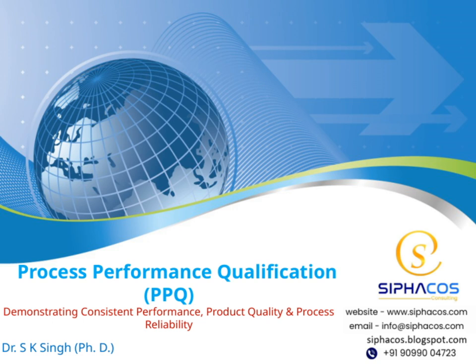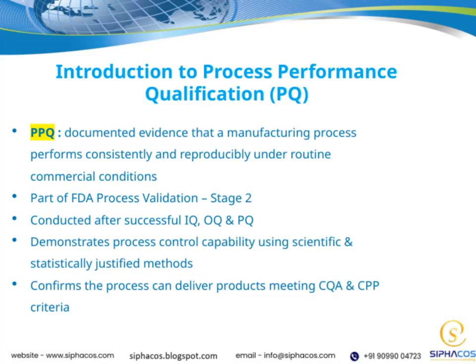So let's get started. Now, let's talk about PPQ, or Process Performance Qualification. This is the stage where we gather documented evidence to show that a manufacturing process performs consistently and reproducibly under routine commercial conditions. Essentially, it's about proving that the process is reliable in real-world production settings. This step is part of the FDA's Process Validation Framework, specifically Stage 2. It's conducted after we've successfully completed the installation qualification, operational qualification, and performance qualification. So it's like the final stamp of approval that confirms our process is under control.